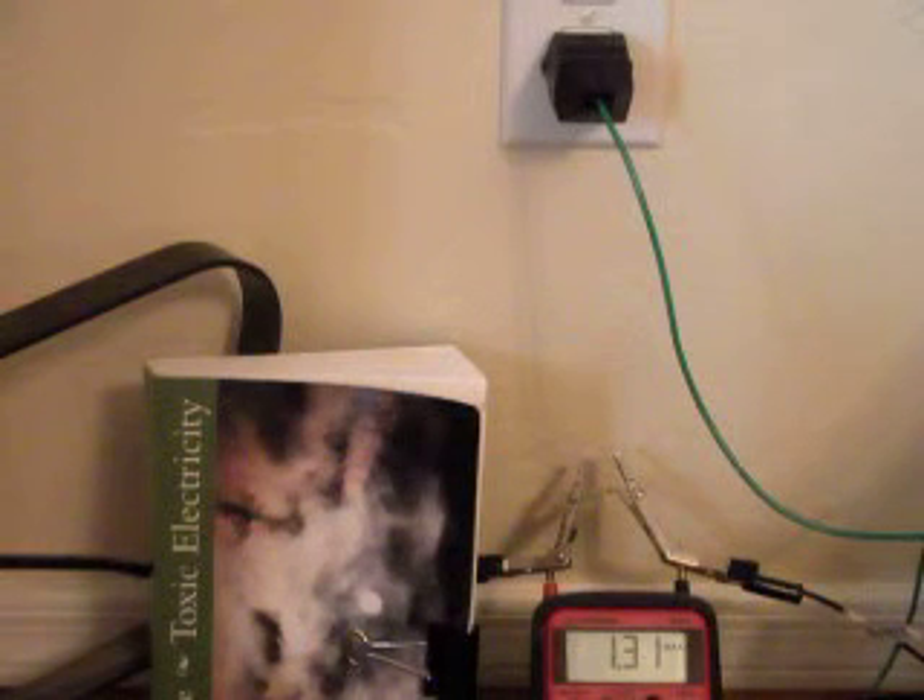So that's stray voltage. My conclusion with stray voltage right now, particularly at my home, is that you don't need this resistor. I actually researched the dry human body voltage, and this meter has an input impedance probably in the range of megaohms, which also matches very well the dry human input resistance — that's typically in the range of megaohms as well. That's the reason why I generally don't put the resistor in: I research the dry human body voltage exposure as opposed to the wet human body voltage exposure, which was very well researched back in the 1970s during the research done with cows in milking parlours.